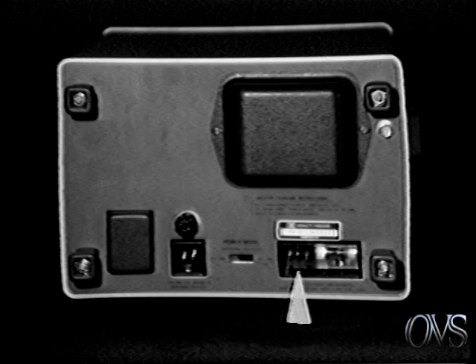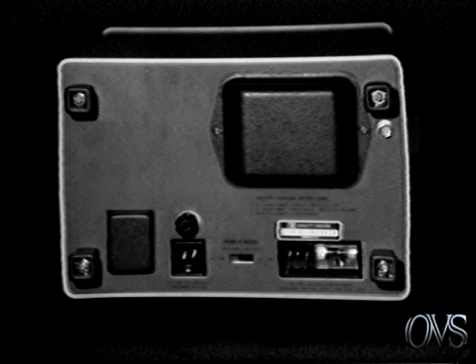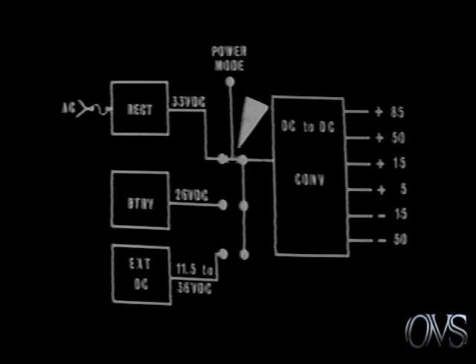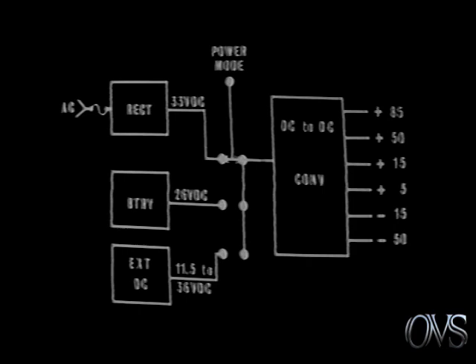The 1700 series scopes accept power from three sources: AC line, an optional internal battery, or external DC. The AC input is rectified, filtered, and limited to approximately 33 volts DC. Therefore, at the power mode switch, there is a selection of three DC voltages. This DC can range from 11.5 to 36 volts depending on the source selected.